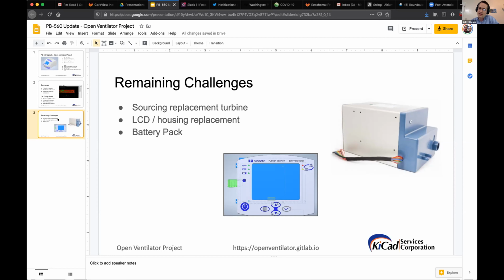And the last element that I did neglect to list on this presentation is the O2 mixing regulation chamber. And so the valves for oxygen control and the mixing are not currently available from the Medtronic stock. So we're looking for options to replace that at the moment. So those are the four remaining major challenges, kind of our long tent poles at the moment.